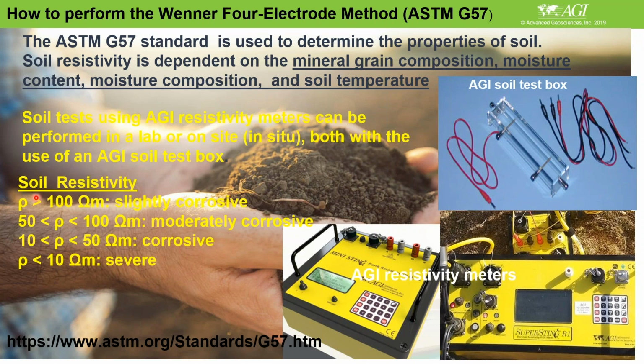What you get at the end on this sample is a measurement that our system is designed to provide in centimeters, because the area is fixed. We make this calculation automatically, and then you can easily convert all this measurement to ohm meters. Soil resistivity will then be reflected, because apparent resistivity and real resistivity are the same thing here, since everything is homogeneous. There is no heterogeneity at all in here. I mean, it's in the condition. All material is the same, so this apparent resistivity measurement can be reflected as the real resistivity measurement.